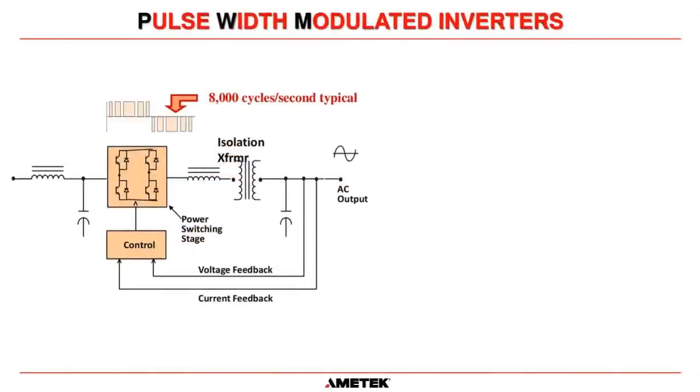All right, that's the ferro system. The next thing we're going to look at is a pulse width modulated type system. So we're taking DC in here, going to an inverter bridge, and we show transistors there, IGBTs in the box. And we're going to be putting a synthesized AC waveform on the primary. Then we're going to hang a capacitor on the secondary, and it's going to smooth out the waveform, give us a nice pretty waveform. Now in this type system here, we have feedback networks.